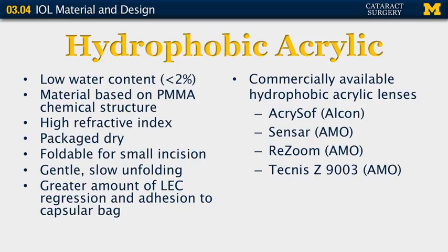The hydrophobic acrylic lens has a lower water content, so this lens is packaged dry. It has a structure chemically based upon the polymethyl methacrylate of the original intraocular lens implants. It has a relatively high refractive index and is foldable for small incision use. This lens has a very nice, gentle, slow unfolding that eases use in the operating room. There tends to be a greater amount of lens epithelial cell regression, and the lens adheres nicely to the capsular bag, reducing the likelihood of capsular opacification requiring YAG laser capsulotomy. The Alcon AcrySof line of lenses falls into this hydrophobic acrylic group.